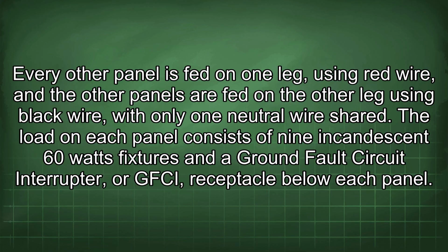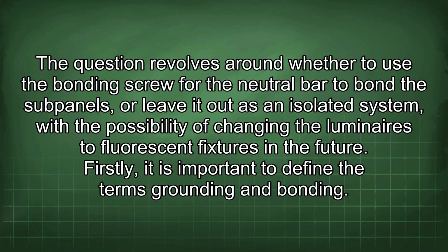The load on each panel consists of 9 incandescent 60 watt fixtures and a ground fault circuit interrupter, or GFCI, receptacle below each panel. The question revolves around whether to use the bonding screw for the neutral bar to bond the subpanels, or leave it out as an isolated system, with the possibility of changing the luminaires to fluorescent fixtures in the future. Firstly, it is important to define the terms grounding and bonding.